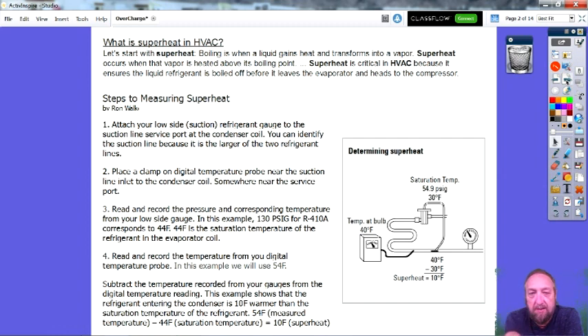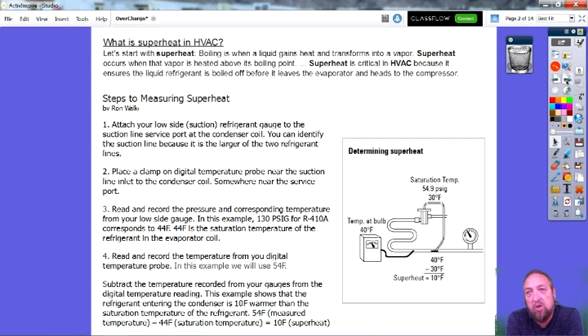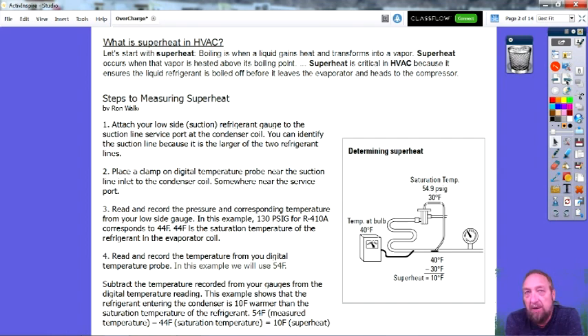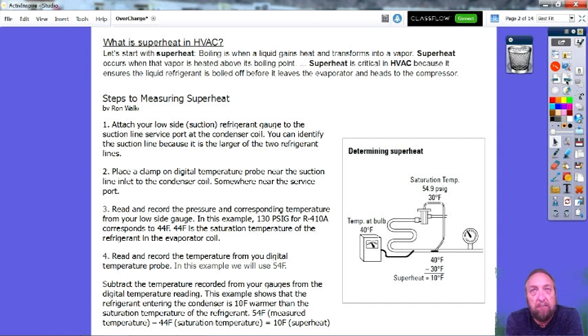Water boils at 212 degrees Fahrenheit. At 215 or 230 degrees, anything above 212 degrees becomes superheat — where the steam is above the boiling point. Superheat is critical in HVAC because it ensures that liquid refrigerant is boiled off before it leaves the evaporator and heads to the compressor.